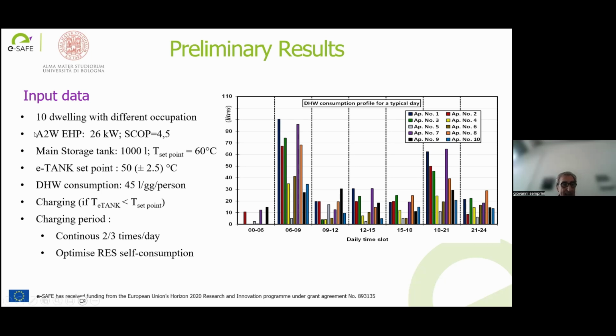We consider 10 dwellings with different occupation, from 1, 2 persons up to 5 persons for each dwelling. We consider an air-to-water heat pump with a seasonal coefficient of performance of 4.5, a main storage tank of 1,000 liters with a set point of 60 Celsius. The set point of each tank in each dwelling is set at 50 Celsius.